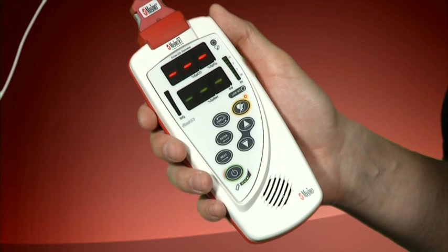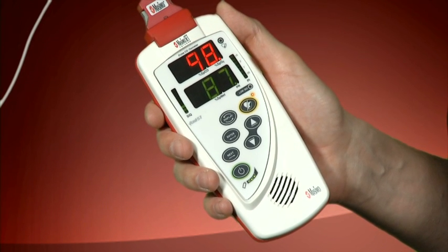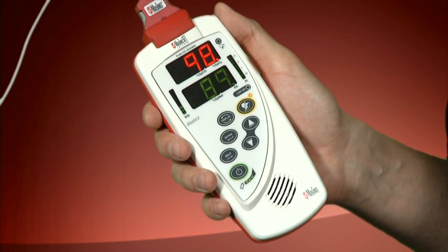The first screen to be displayed will be the SpO2 and pulse rate screen. The SpO2 value will be on top in red. The pulse rate will be on the bottom in green. The default configuration is for the device to display SpO2 and pulse rate first. You can, however, elect to make SpCO and SpMet display first. The operator's manual contains directions on how to change the default display upon startup.